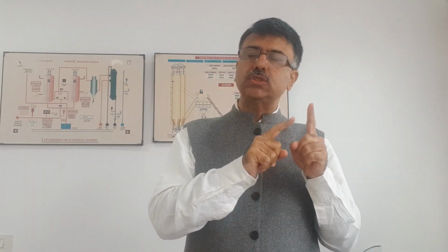So Solcon always has to be installed near the DG or near the grid panel, within 10 meters. Absolutely. After ACDB would be better. Where the ACDB cable is terminating into the main evacuating panel, that would be the best place. The guiding point is that the distance of CT to Solcon should not be more than 10 meters.